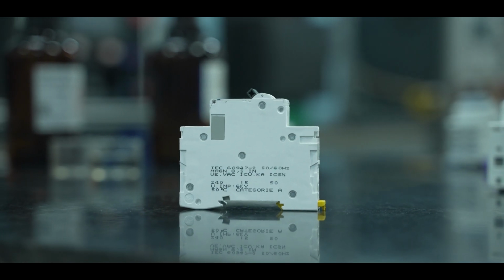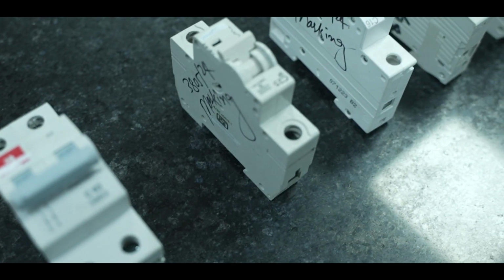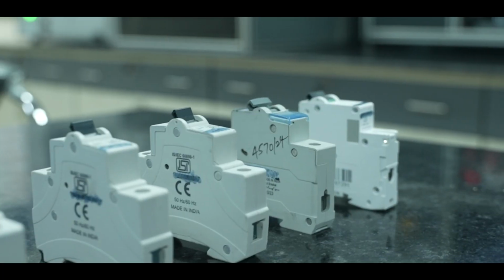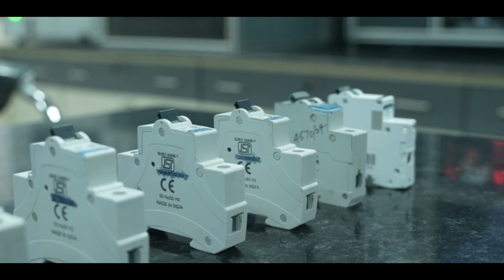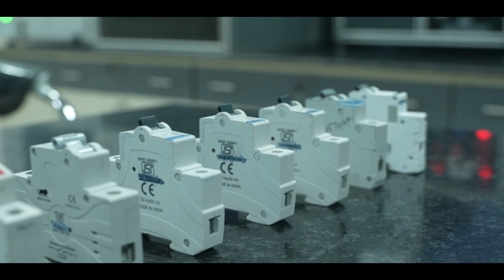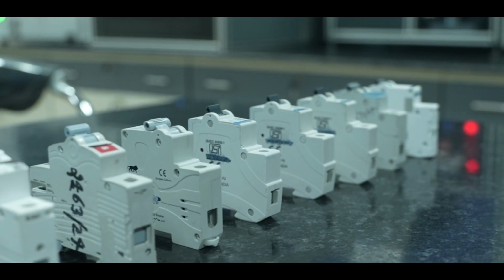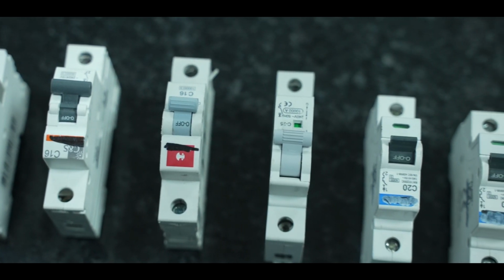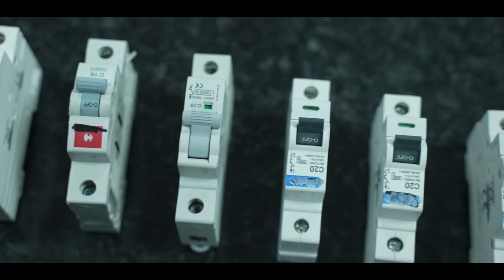Marking and general test. This test ensures that all required information such as the manufacturer's name, product type, ratings, and compliance with IS 60898 is correctly marked on the MCB. It also includes verifying the general construction of the device for compliance with the standard.